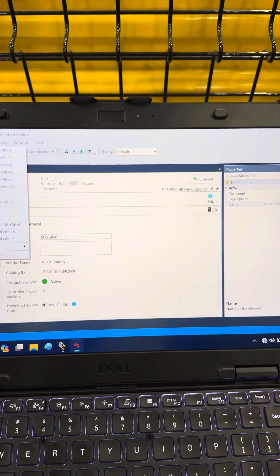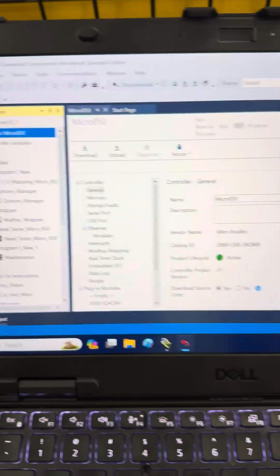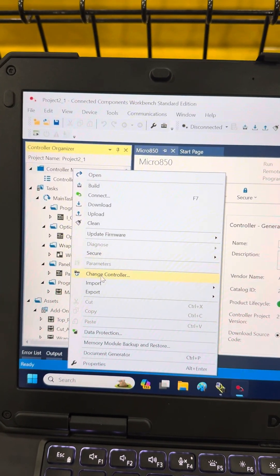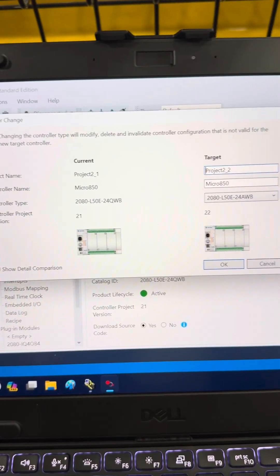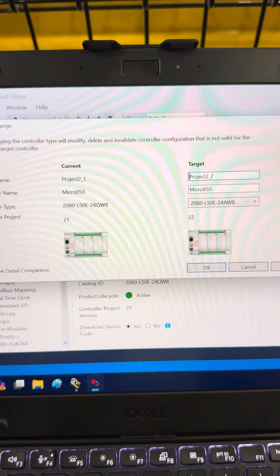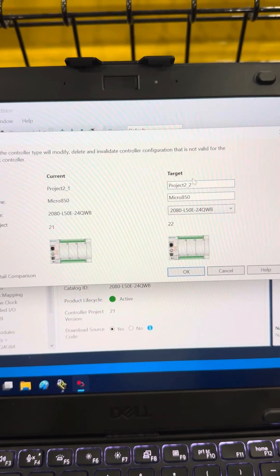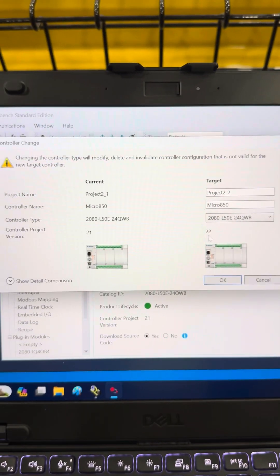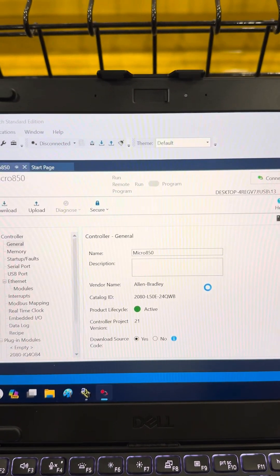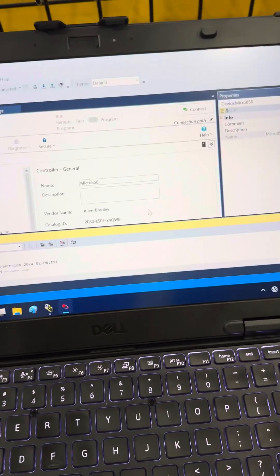Now I want to view the controller organizer. This is my current program. What I need to do is right-click here and I need to change the controller there. Notice they don't match — this is a QWB, this is an AWB. So we've got to change that to AWB. Project 2.2 — there's your version 22 right there. Hit OK. Now what we've done is we've changed the project to version 22.